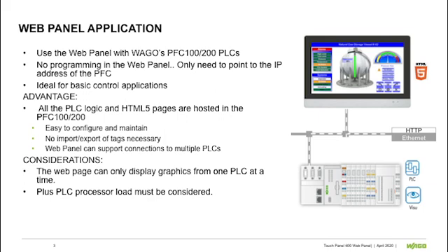The advantage of this architecture is that the PLC logic and HTML5 pages are contained in the PFC controller. This makes configuration simple. The logic and graphic pages are in one application, making it easy to develop and maintain. There's no need to import or export tags between the PLC program application and the HMI engineering application. Everything is one program. So if you need to make changes in the future, there's only one application to modify.